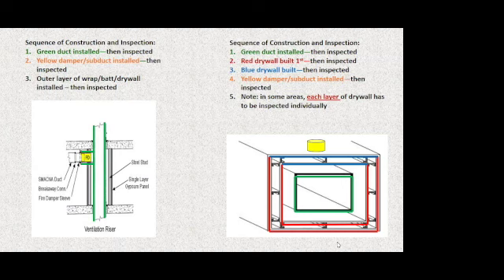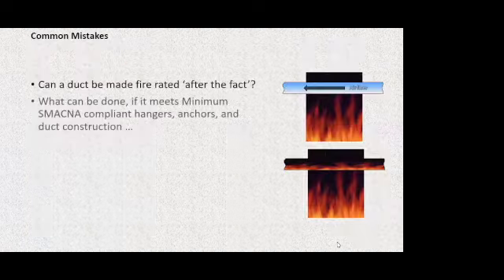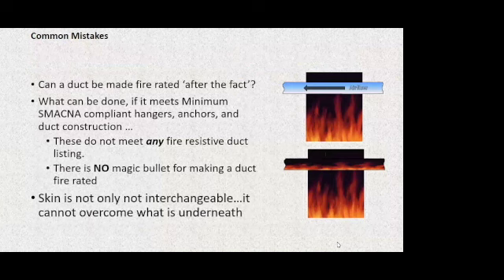Very, very often we're using fire rated duct systems for economy, speed, schedule, and those are all good things. We want a building that can go up quickly. We want one that can go in cost effectively. But when we do that, we need to pay attention to the fact that, okay, I can skip 2 out of 5 inspections if I use the fire rated duct system. But if I do, am I going to pass those inspections because I've done it correctly, that I've used the correct product? That's the question. That's the question. Because we can't do it after the fact.